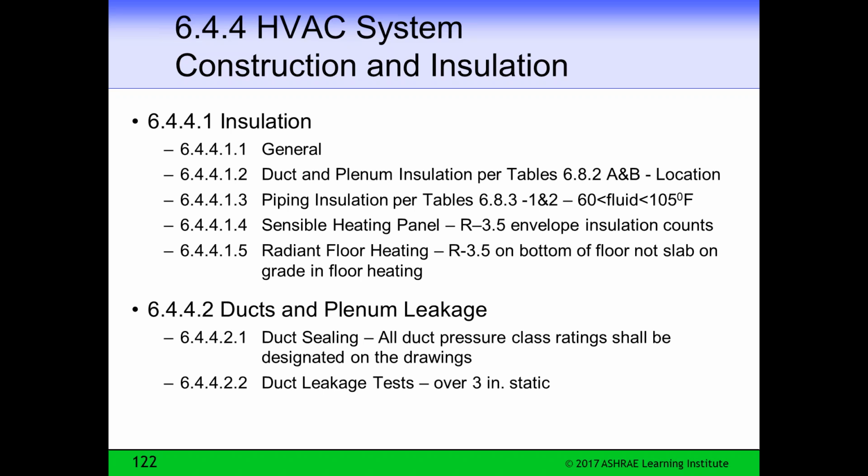We met with the contractors, and if it's that simple, where they know they need class A everywhere, it pays back. They're not charging much extra. They're just going to seal it. And duct leakage is a tremendous energy loser, so we want it all sealed to class A.